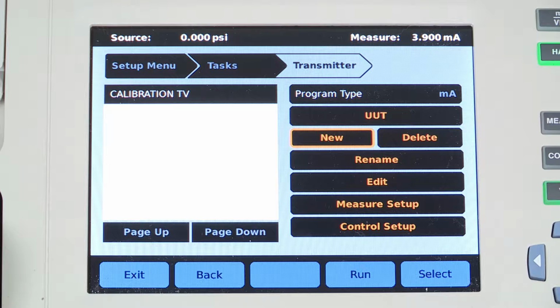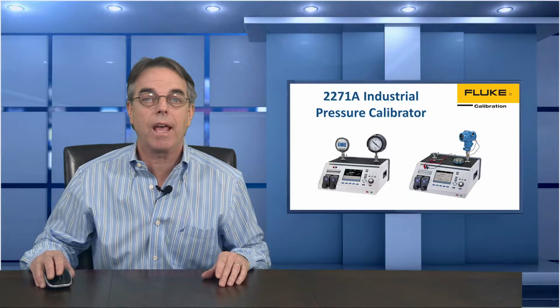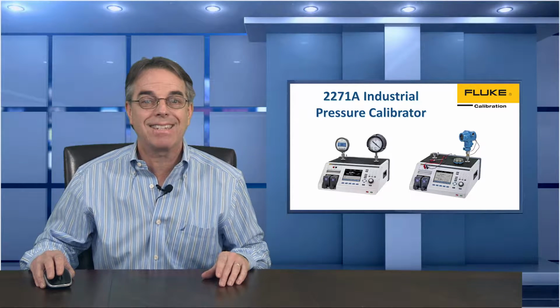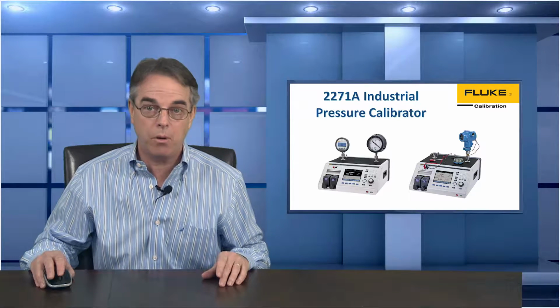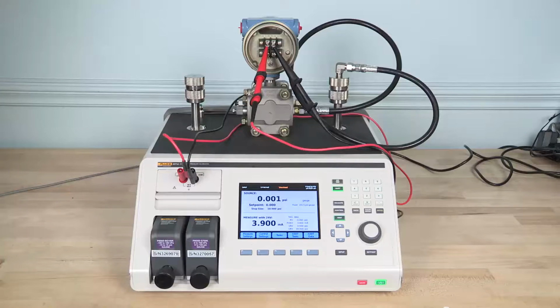The 2271A also allows you to set up and store built-in tasks. A task is a sequence of pressure points along with some information about the test device, such as the range and the accuracy specifications. What I really love about the 2271A is that when the automated calibration is complete, it creates an Excel file with all the test data that you can easily transfer to a computer. Take a look at this video.